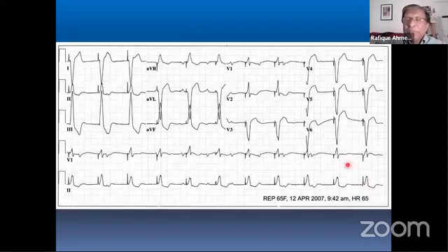So you have to remember this. With pacemakers, when the battery gets depleted, there are different mechanisms of conserving the battery. Medtronic has a default mode that if a Medtronic pacemaker reaches ERI, it goes to a rate of VVI 65. This was a Medtronic pacemaker. A St. Jude pacemaker will go to a fixed rate at the programmed lower rate, dual chamber.